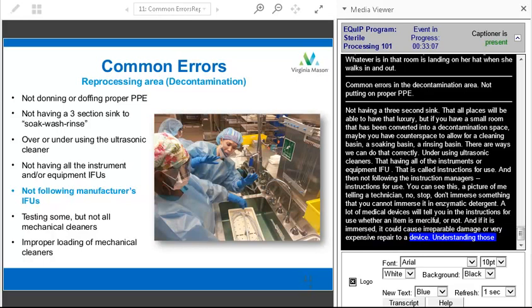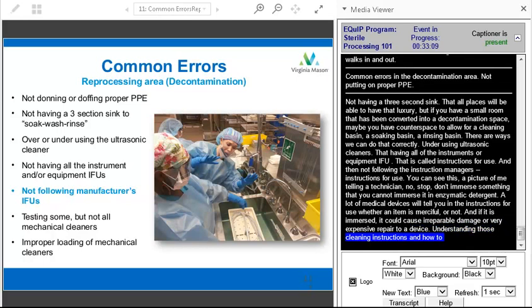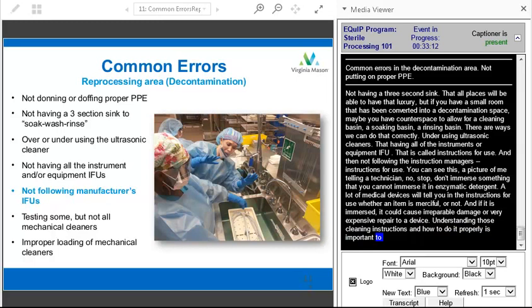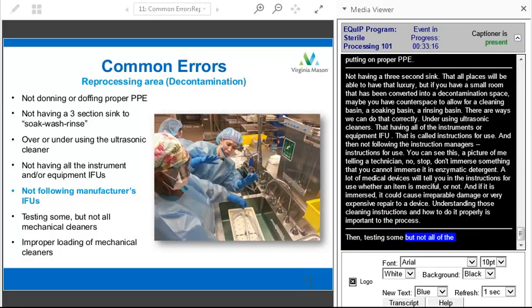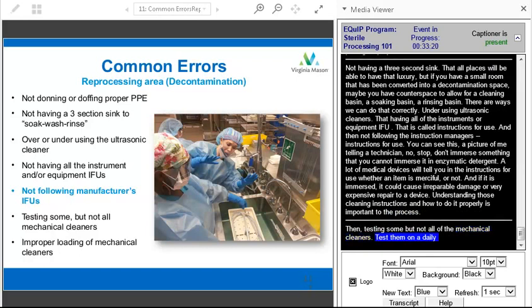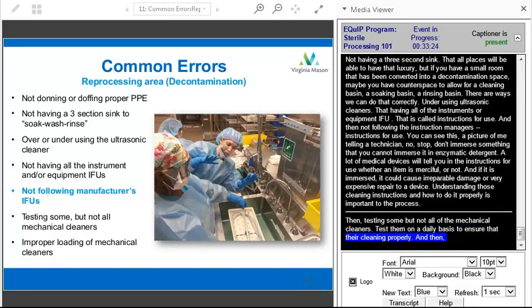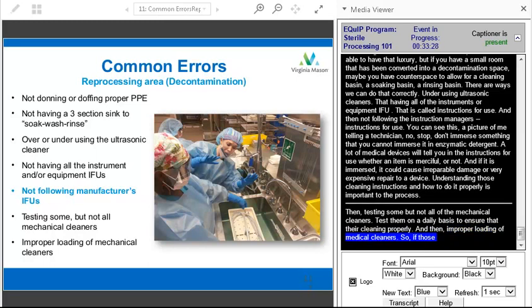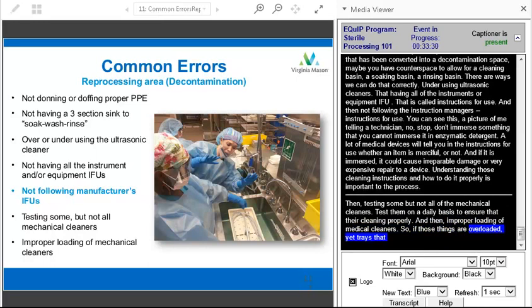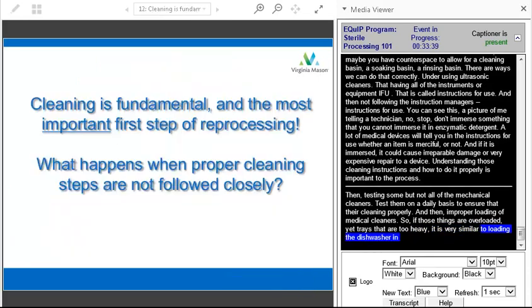Then testing some, but not all of the mechanical cleaners. If you have washer disinfectors, being able to test those on a daily basis to ensure that they're cleaning properly is important. And then improper loading of mechanical cleaners. If those things are overloaded, you have too heavy of trays on those types of things, those impingement arms and that type of stuff. Very similar to loading the dishwasher in your house. If you overload it, things are going to not be cleaned as effectively as they should.